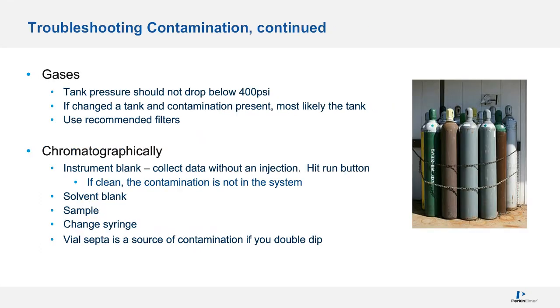Gases are a source of contamination, so the tank shouldn't drop below 400 pounds. If you change a tank and contamination is present, it's most likely the tank, because that's the last thing we did. Let's see, syringes could be a source. Oh, vials. Wash and waste vials should be replaced. The waste vial should be inspected to make sure it's as empty as possible, because that will bring contamination as well.